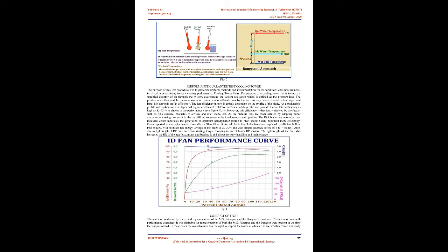The design wet bulb temperature is determined by the geographical location. Usually the design wet bulb temperature selected is not exceeded over 5% of the time in that area. Wet bulb temperature is a factor in cooling tower selection. The higher the wet bulb temperature, the smaller the tower required to give a specified approach to the wet bulb at a constant range and flow rate.